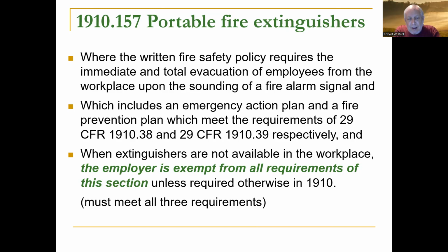And when fire extinguishers are not available in the workplace, the employer is exempt from all requirements of this section unless required otherwise in 1910. So in other words, it has to mean all three of those things. You have a written fire safety policy, and your policy states that all employees are going to get out. That's it. Everybody out. Nobody's going to stay to fight the fire. Nobody's going to stay to operate any equipment or shut down anything. Everybody is going to get out when the fire alarm goes off.